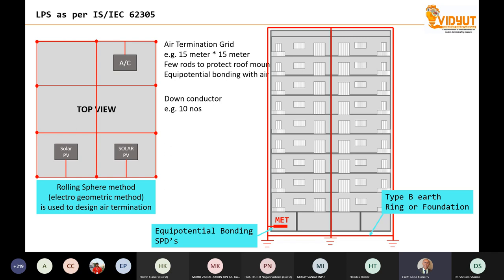And in addition, we have to make equipotential bonding. Equipotential bonding means the mesh and the metal parts of these electrical apparatuses are interconnected. This is the normal way of doing air termination. Now for designing the air termination and positioning the rod, we also have the electrogeometric sphere principle, the rolling sphere method, which has been followed across the globe for several years. Especially in the lightning protection of transmission lines, millions of kilometers of transmission lines across the globe are designed with this particular principle, rolling sphere electrogeometric modeling.